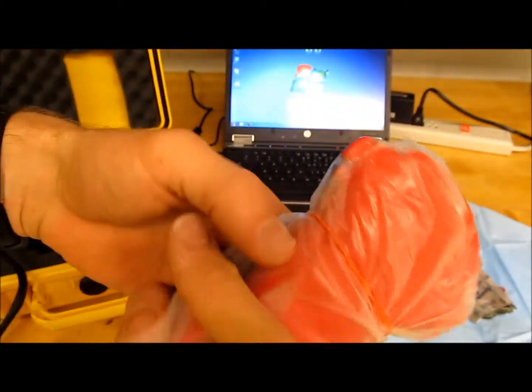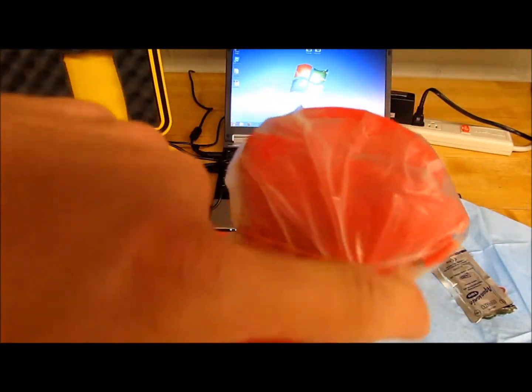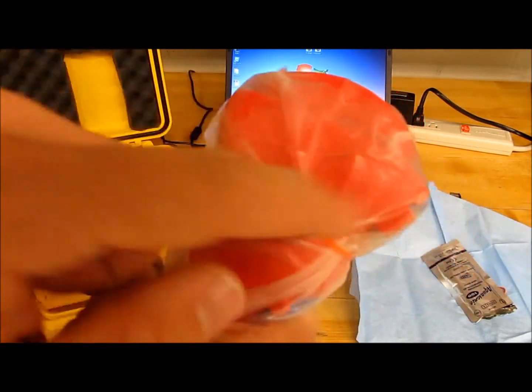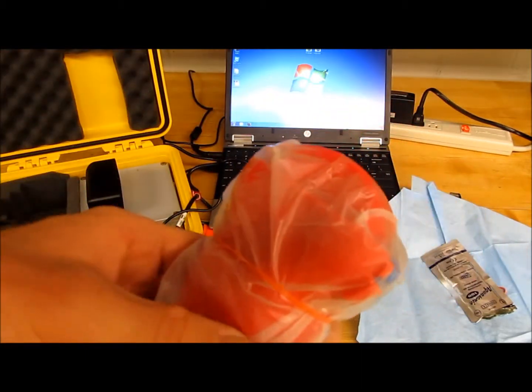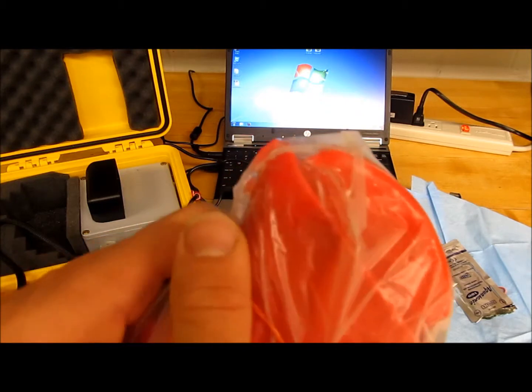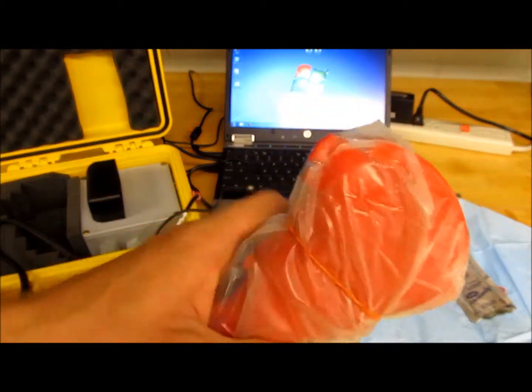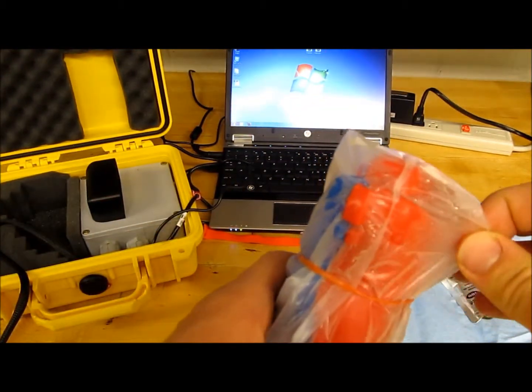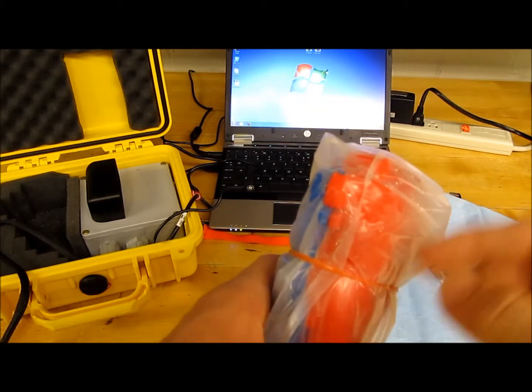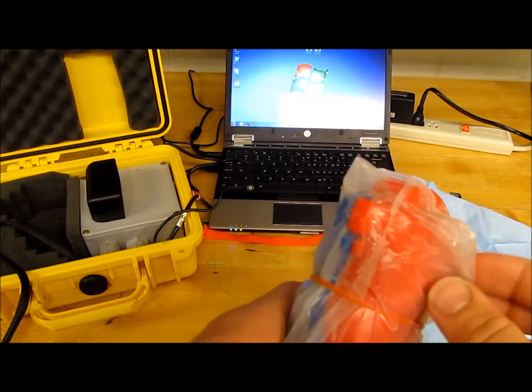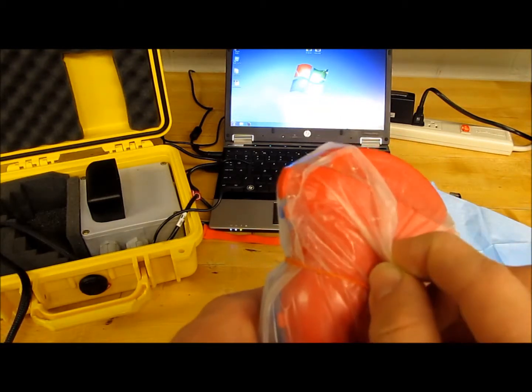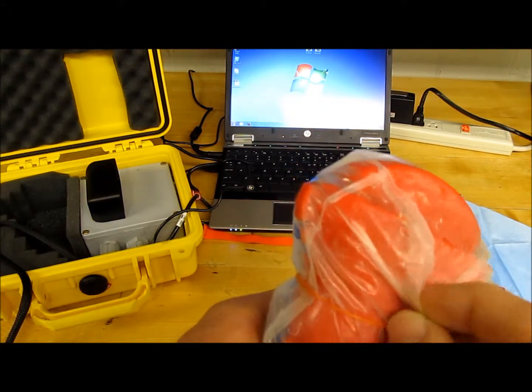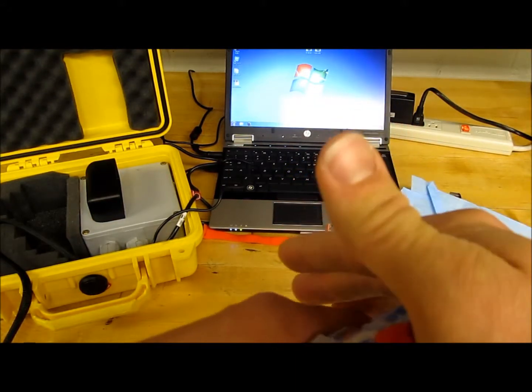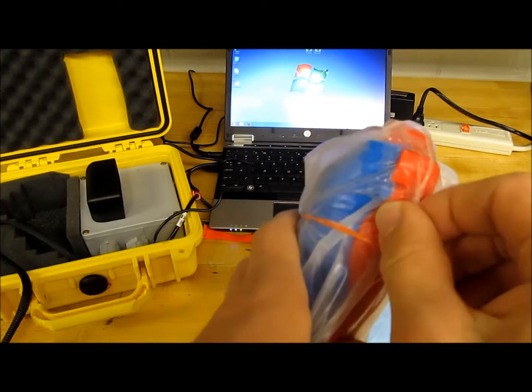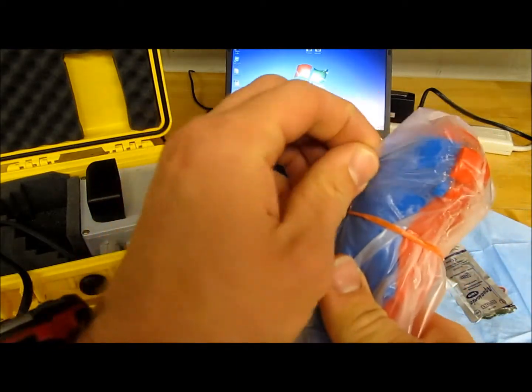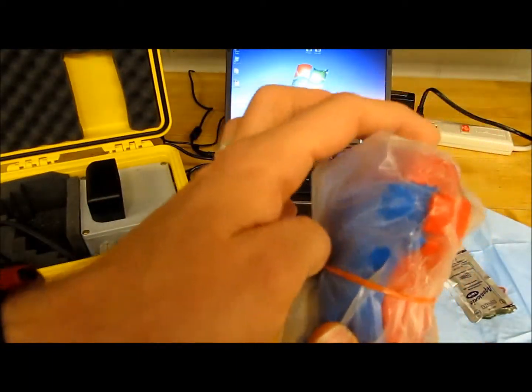the bag. There's a couple of notches here. There's a few bigger notches here and some smaller notches here. You can use whichever ones you prefer to secure the bag over the probe. Now we want to make sure that the bag is relatively loose between the rubber band and the ultrasound probe. If it's not loose and we get some force pulling down like this, then our force reading will be less accurate. So we want to make sure that the bag is nice and loose the whole way around between the rubber band and the face of the transducer.